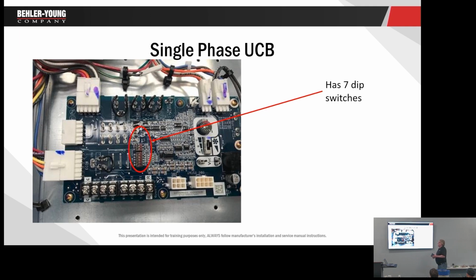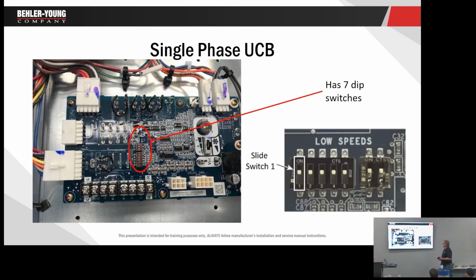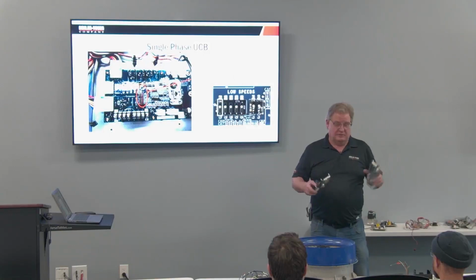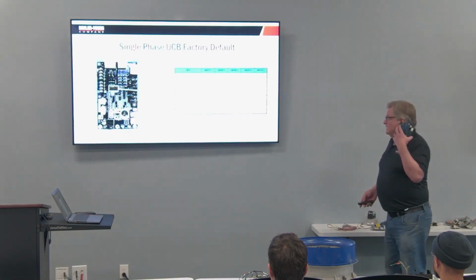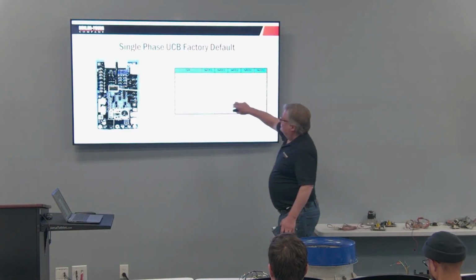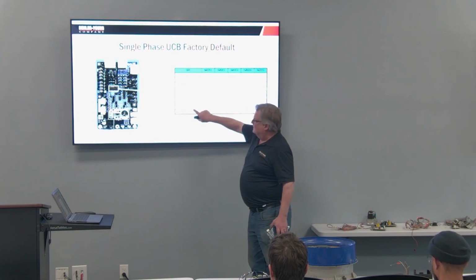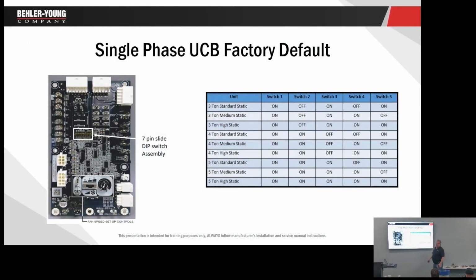Okay. So the single phase has 7. These 5 here have to do with what blower's in that unit. So just put them back. If you took the old board with you and forgot to bring it back, look on the tag by the wiring diagram, and it'll tell you where the switches go. Okay. Now, this is kind of how it lays out. So for instance, we've got a 5-ton standard, medium, high, and the switches go in different positions to tell the unit what size unit it's in. Again, this is only a single phase.